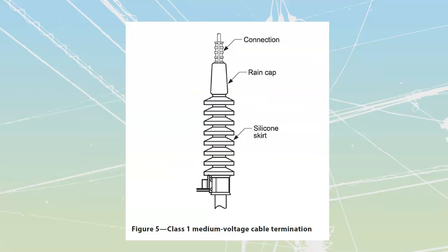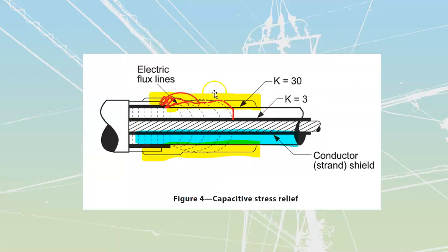We've got a couple of different classes of terminations as well. IEEE defines 3 classes, and our high voltage is assessed according to IEEE Class 1, 2, and 3, but we really only use 2 of these. We use Class 3, which gives us stress relief only, and that's used indoors or inside transformers that have a rain shield or things like that.